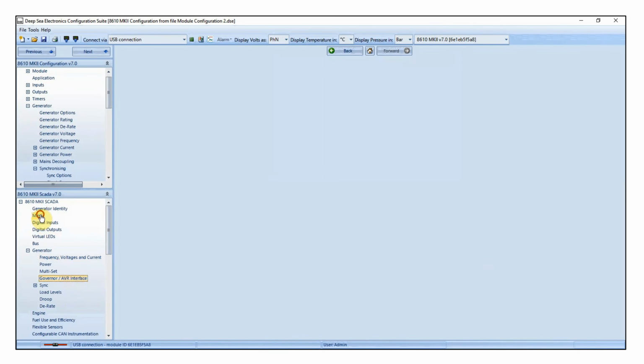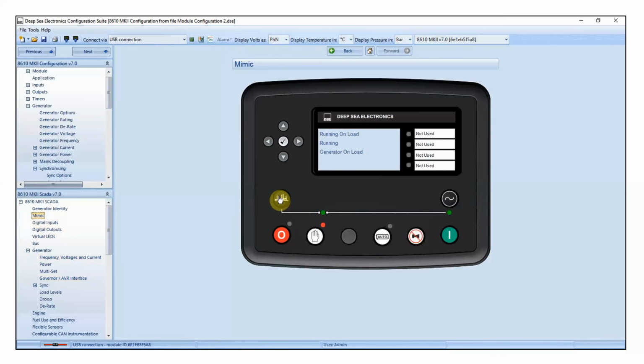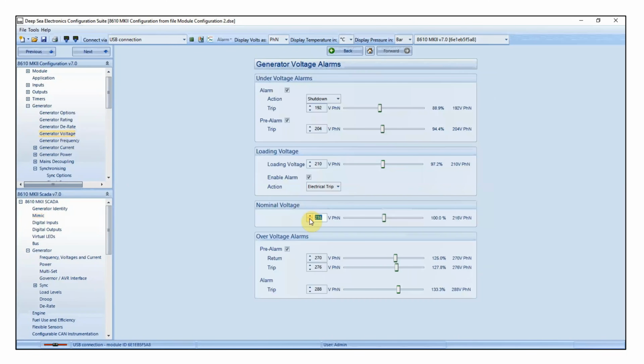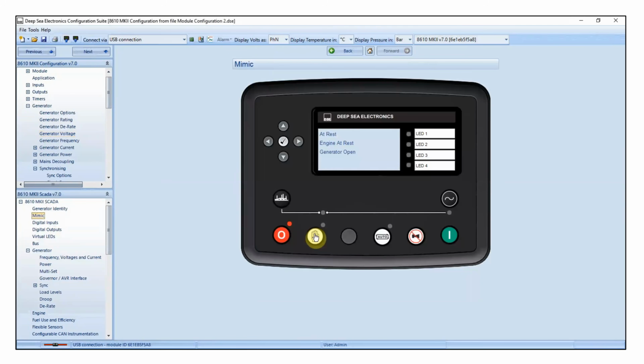So all we're going to do now, again, is tell the generator breaker to open and stop the generator. But again, remembering, very importantly, to go back to the generator voltage section and change the nominal voltage back to what it should be. In our example, 240 volts. At this point, what I like to do after I've written the configuration is just start the generator up again and close the generator breaker. That will then ensure that the generator runs, or should I say, confirms that the generator runs at the correct voltage and frequency, basically proving that you've remembered to reset the nominal voltage and frequency.